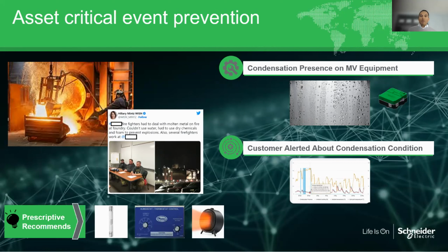So at some point we said, yeah, our dew point condensation presence algorithm has detected that at this rate of temperature, humidity, etc., you have a significant risk of actually having enough condensation inside the equipment to cause a problem. That's good, we know there's going to be an issue, a problem in this piece of equipment.